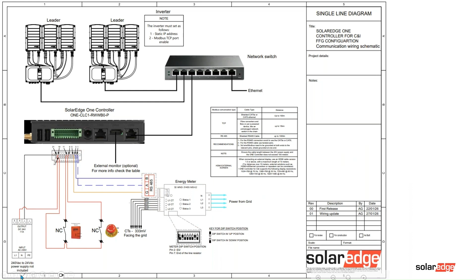For the firefighter feature, you need to connect a 24-volt power supply. Number 19 is plus, 21 is minus. So connect plus to 21 and 19, and include the emergency stop in the circuit to 9. That's how simple it is. So get yourself a 24-volt transformer or power supply and wire it as such.